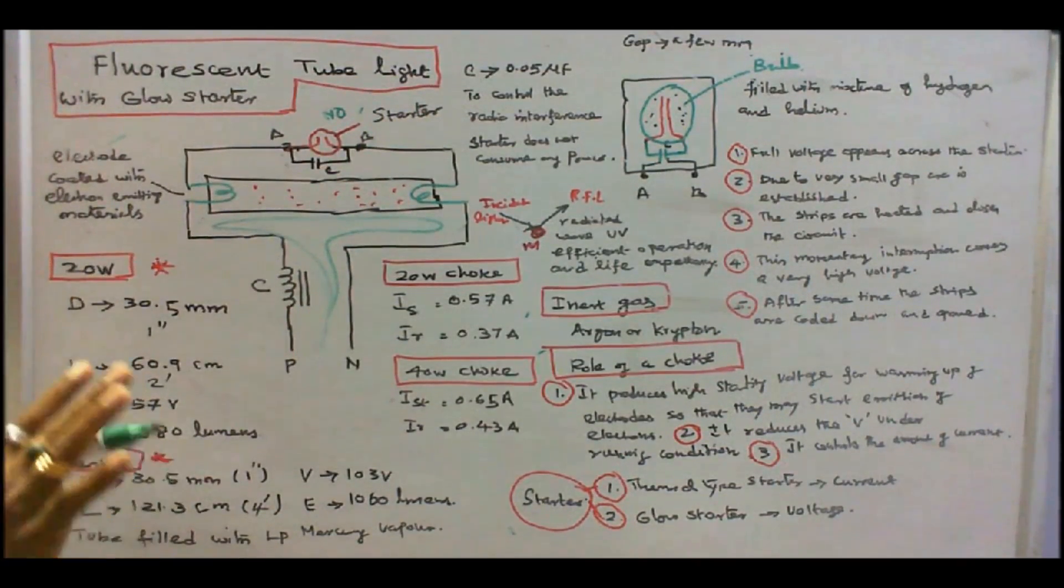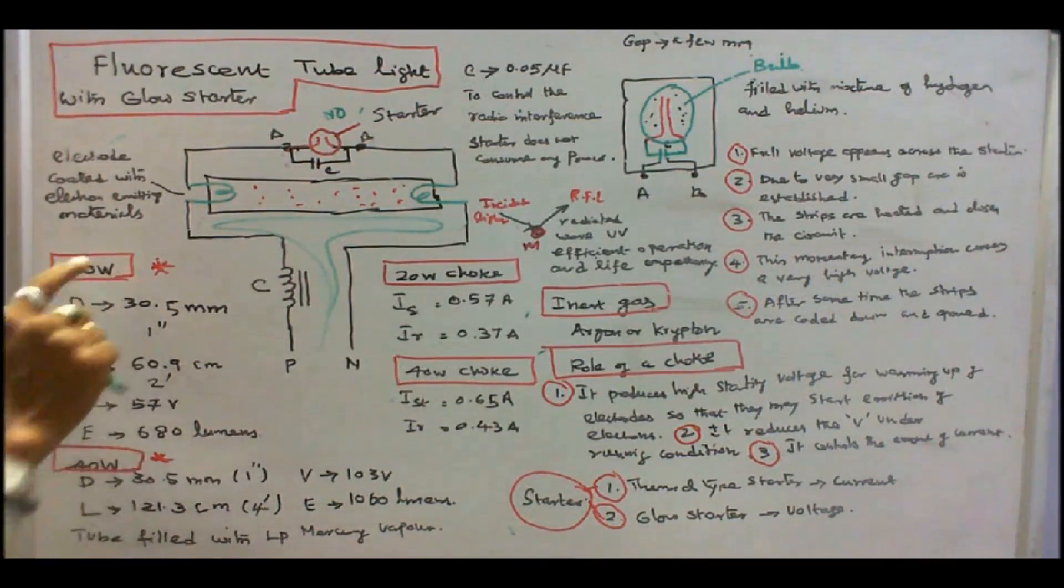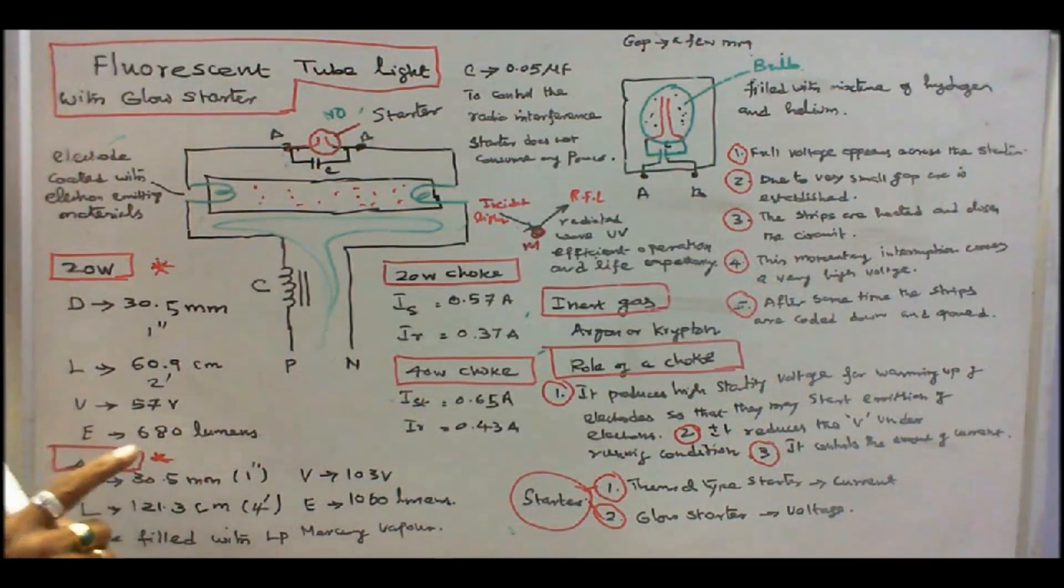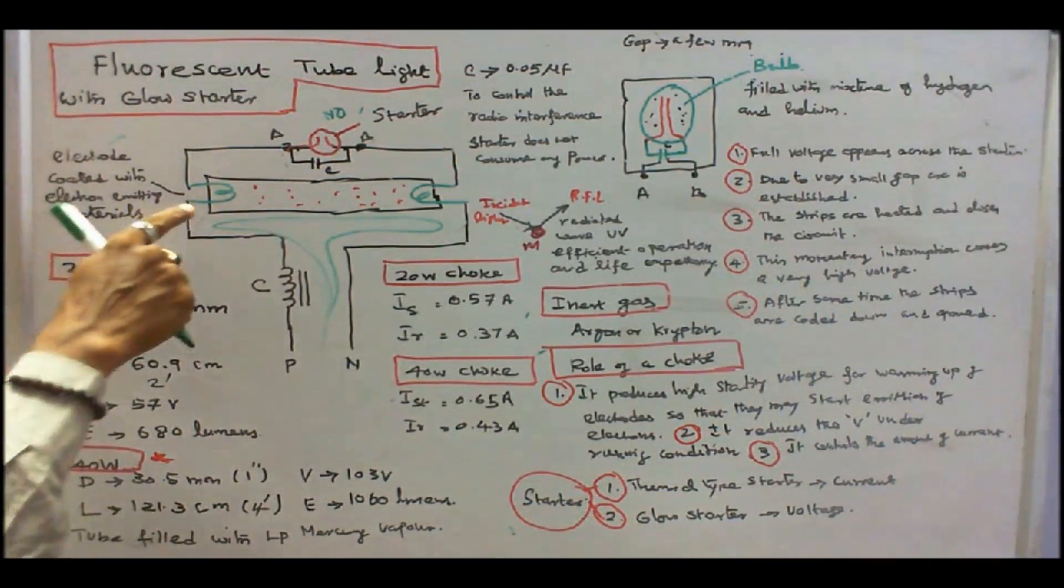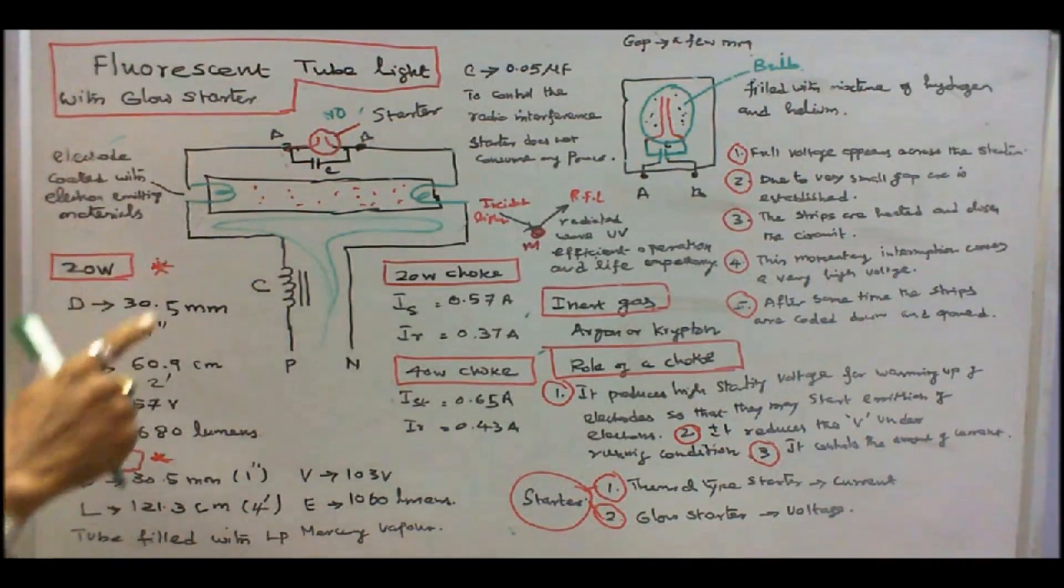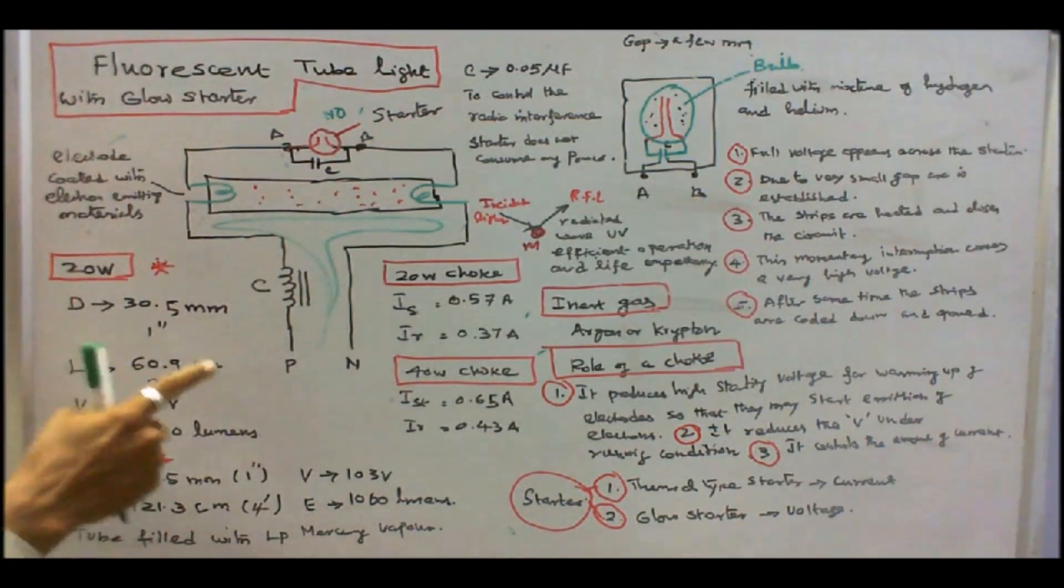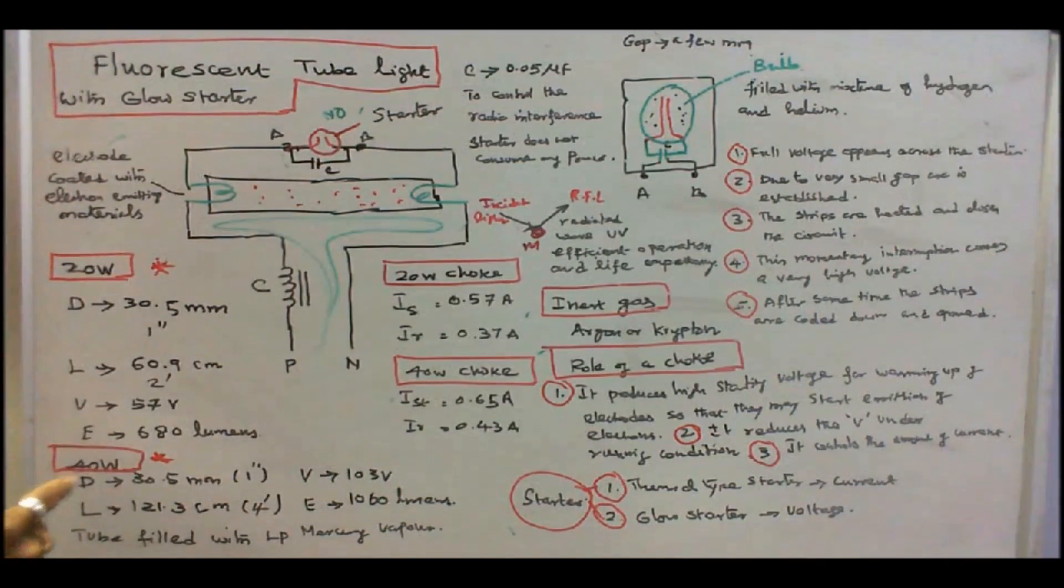Commercially, there are four rating tubelites are available. One is 20 watts, 40 watts, 65 watts, and 80 watts. I choose only 20 and 40. These two are frequently used. The diameter of the tube is, that is tubelite, diameter is 30.5 mm. The length of the tubelite is 2 feet. Its operating voltage is 57 volts. Lumen output is 680 lumens.